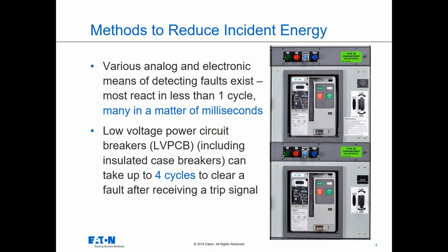So how do we get to reducing that incident energy? Well, there's a lot of different methods to detect the fault current as it starts flowing through a circuit breaker. And nowadays, most of the technology has gotten to the point where they react in less than one cycle, many in a matter of milliseconds. There are analog circuitry such as Eaton's patented ARMS technology, electronic means via standard trip units, and then there exists fusing and other things that are also able to act very quickly.